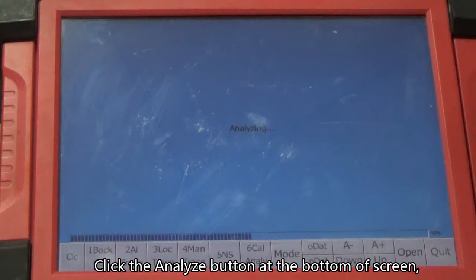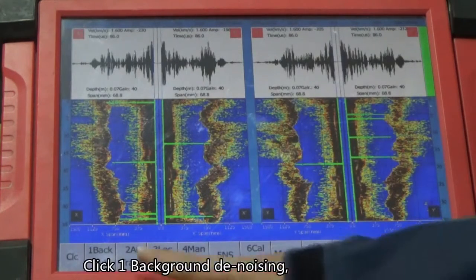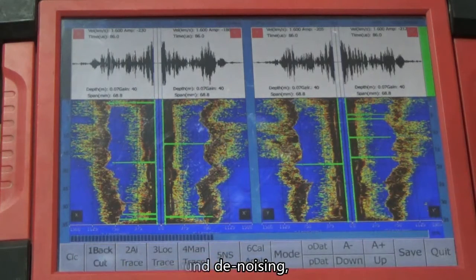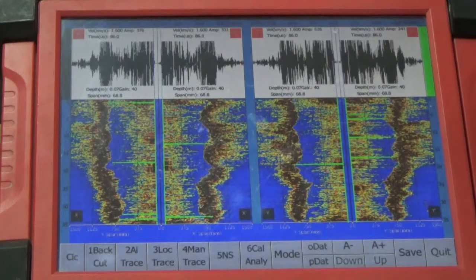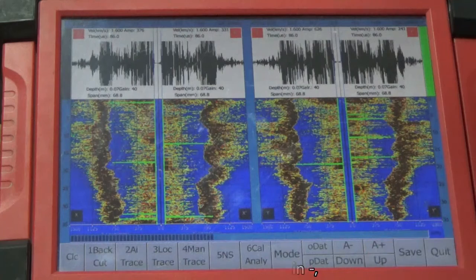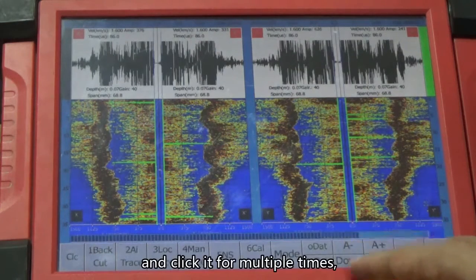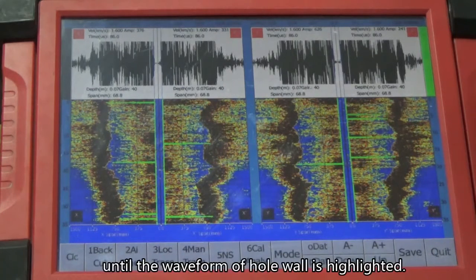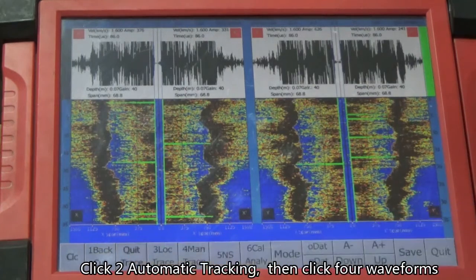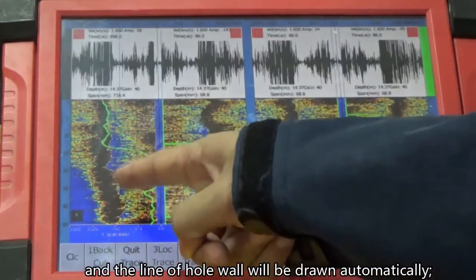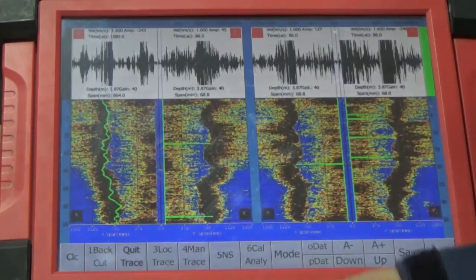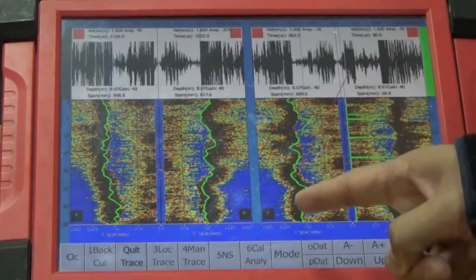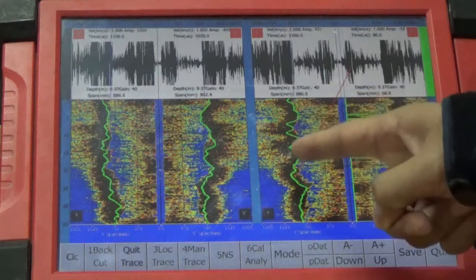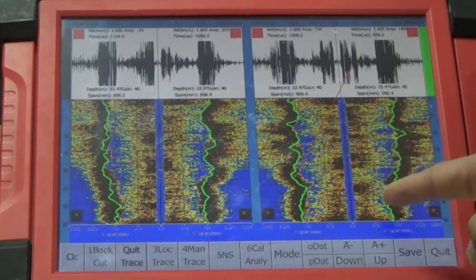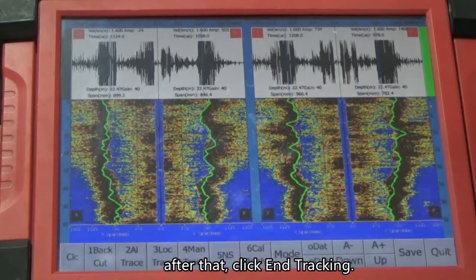Click the Analyze button at the bottom of screen to enter the analysis interface. Click 1 Background Denoising. Gain plus or gain minus at the bottom of the screen, and click it for multiple times until the waveform of hole wall is highlighted. Click 2 Automatic Tracking, then click 4 waveforms of hole wall on the screen in sequence, and the line of hole wall will be drawn automatically. After that, click End Tracking.